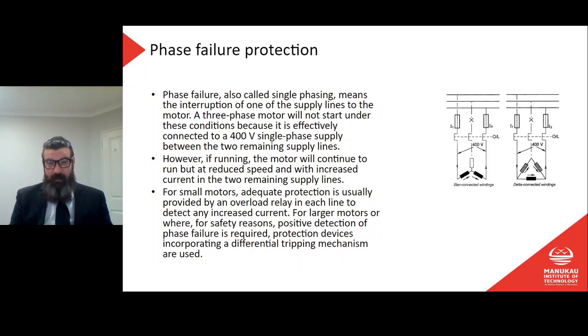It'll run on two phases, but it won't start on two phases, and for the exact same reason that a single phase motor will run on single phase, but it will not start on single phase unless I add a capacitor in there to give me a little bit of phase displacement, or put my two windings out of phase. There's a little head start for you, a little teaser for when we talk about single phase motors. Anyway, if running, the motor will continue to run but at reduced speed with increased current on the two remaining supply lines, as I mentioned earlier.